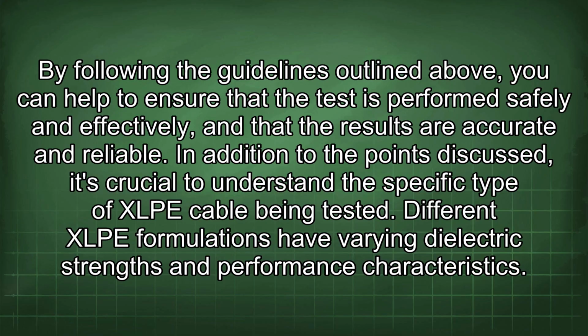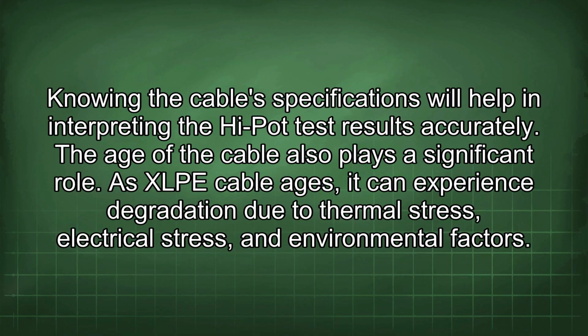In addition to the points discussed, it's crucial to understand the specific type of XLPE cable being tested. Different XLPE formulations have varying dielectric strengths and performance characteristics. Knowing the cable's specifications will help in interpreting the high-pot test results accurately. The age of the cable also plays a significant role.